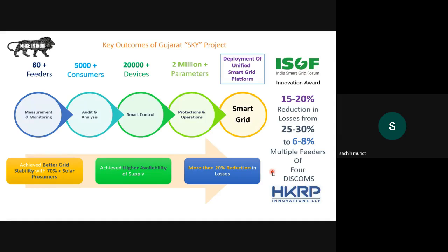Because of this solution and architecture, we achieved better grid stability. In this project, it was mandatory that a minimum of 70% of the farmers or consumers on a particular feeder should be solar consumers, or prosumers. Because of this, we achieved better grid stability, higher availability of supply since daytime three-phase power availability had to be ensured, and more than 20% reduction in feeder losses. That's a huge achievement.